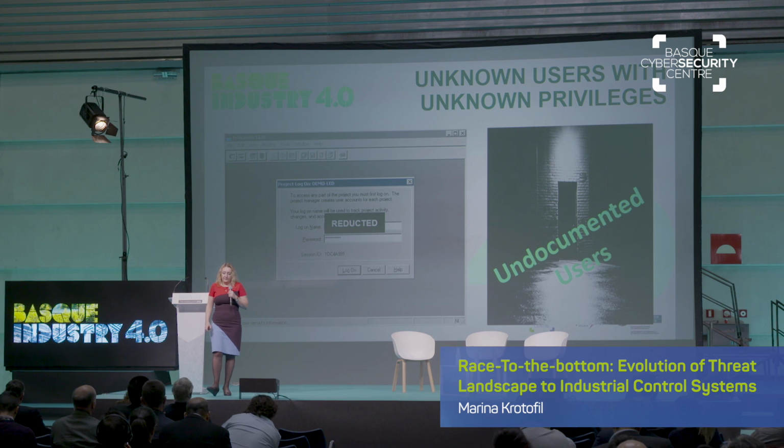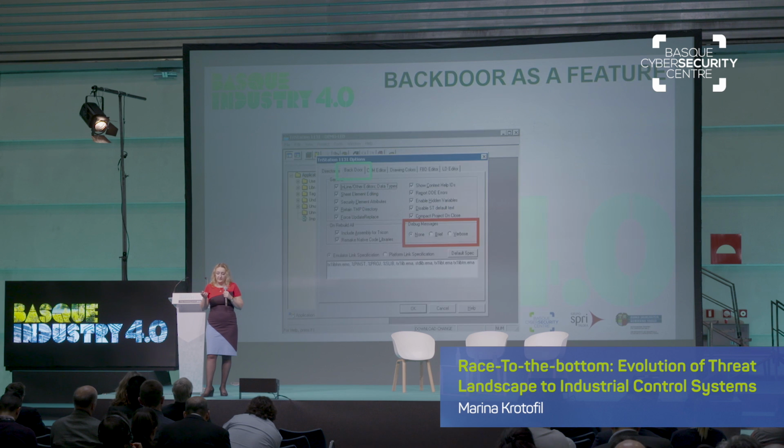For example, while doing this forensic work on the Triton exploit, together with the researchers from Nozomi, we found in the software that there was an undocumented user with very, very high privileged rights. Again, the asset owners, they don't know that the user even exists because it's not documented. But with those privileges, a lot of bad things can happen. And so it gives attackers super powerful access, and those super privileged rights even have a name: backdoor.